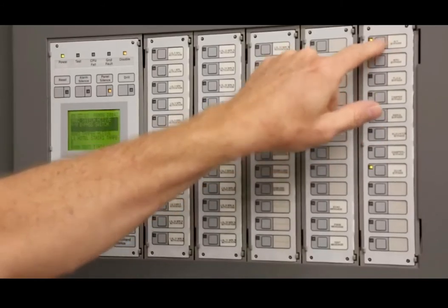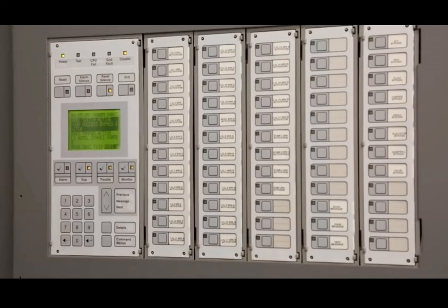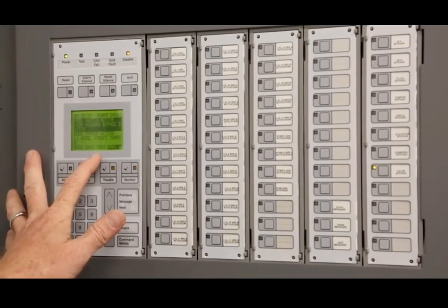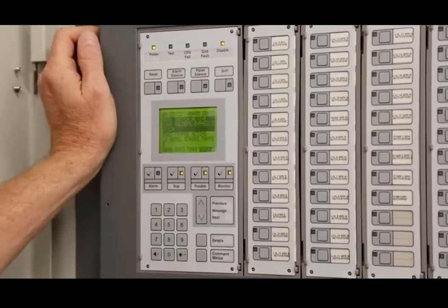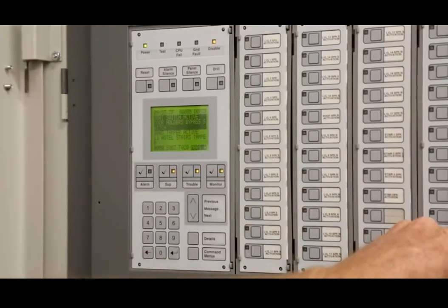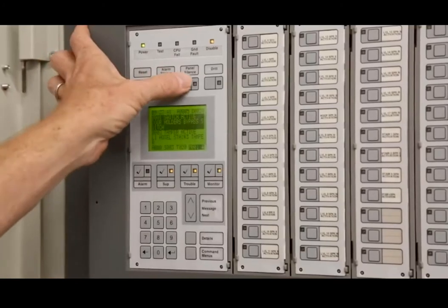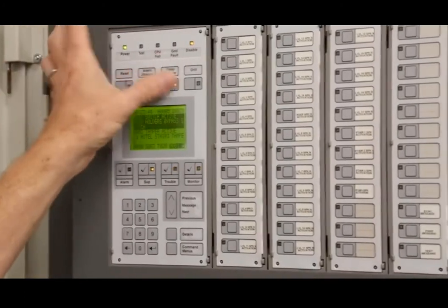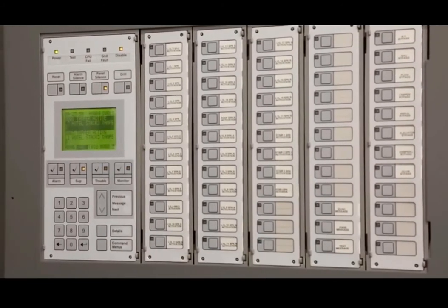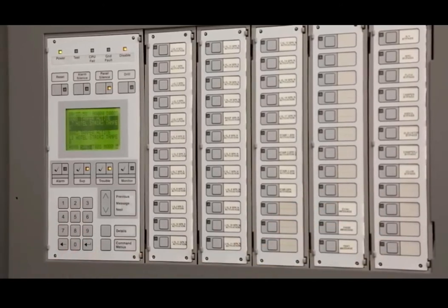To unbypass it, simply hit the button one more time. You notice the light goes off, troubles start going down. Once the troubles are all extinguished back down, they'll do it by itself. And you'll see them count down right now. Okay, we're back down to 20. You can silence the panel, like I said, from any location, that just shuts the panels up. Unbypass the doors, simply hit the button one more time, and it's just a toggle feature. Hit it once, it goes on, hit it twice, it goes off. Okay?